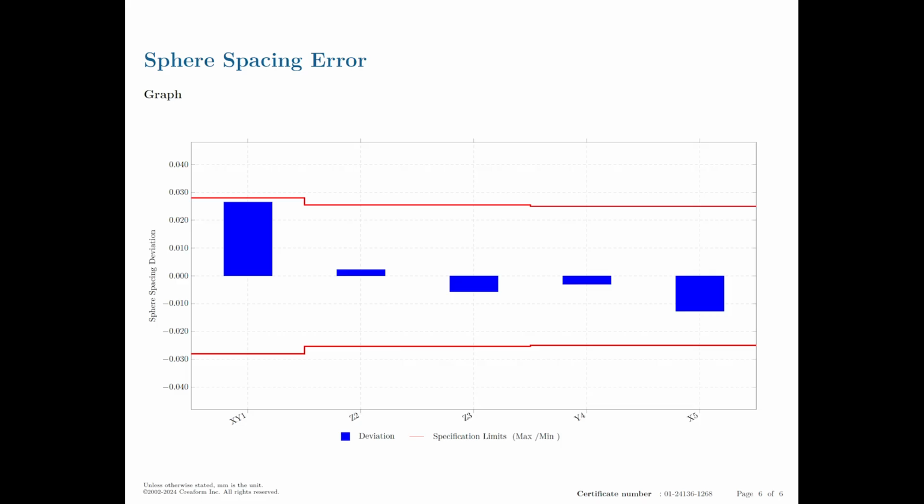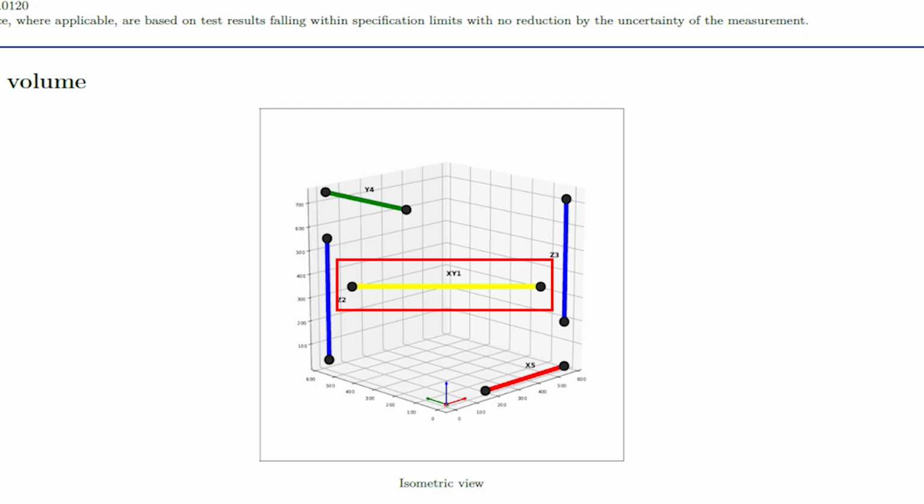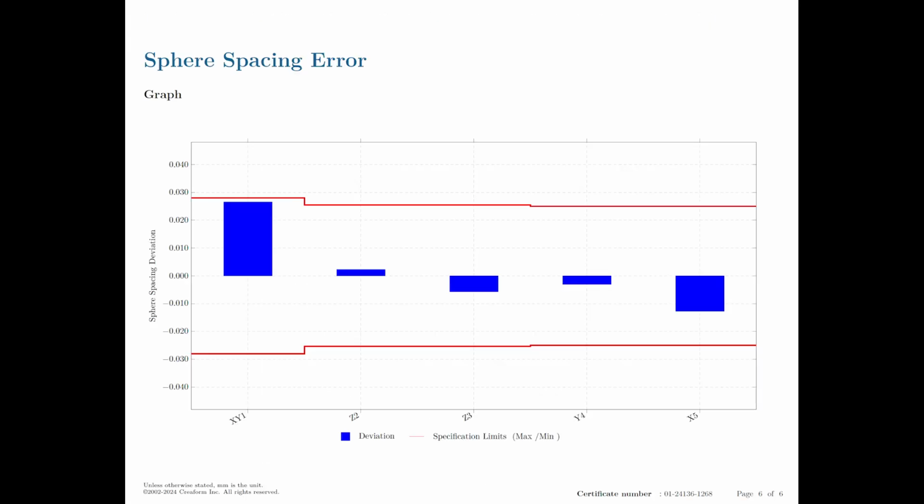And if you look, what is the worst measurement in this case? It's the XY1. That's the one that kind of goes across the volume on an angle. That's typically the toughest measurement to make because you're measuring in length, width, and height. Scanners can be very good in one direction or the other, but to be good in all three directions is a key test. So this gives you a visual representation of those measurements and the accuracy statement made by the manufacturer.